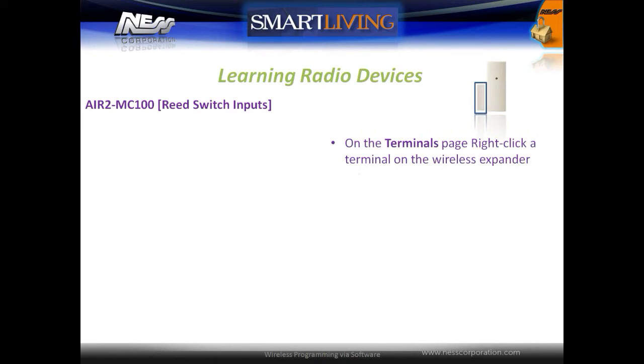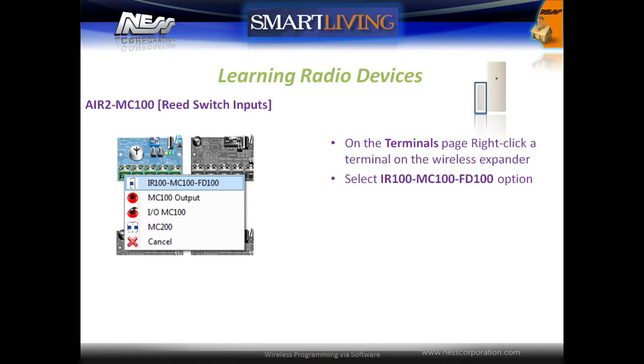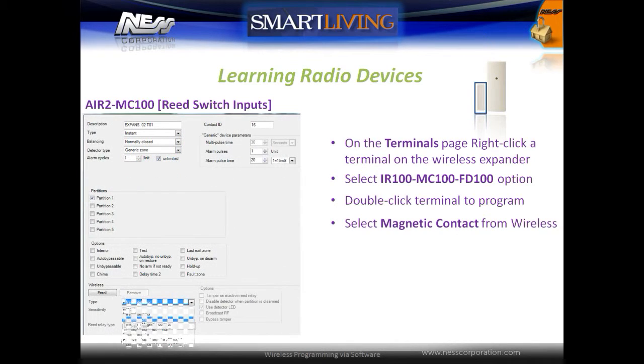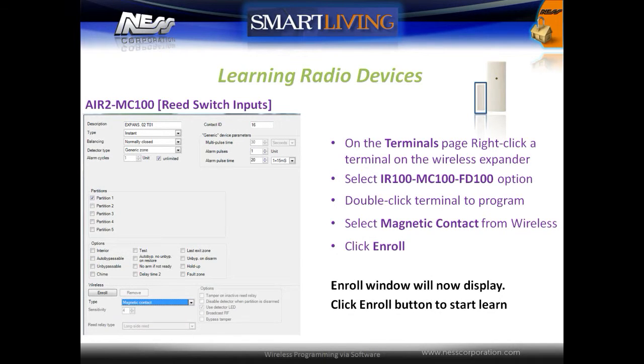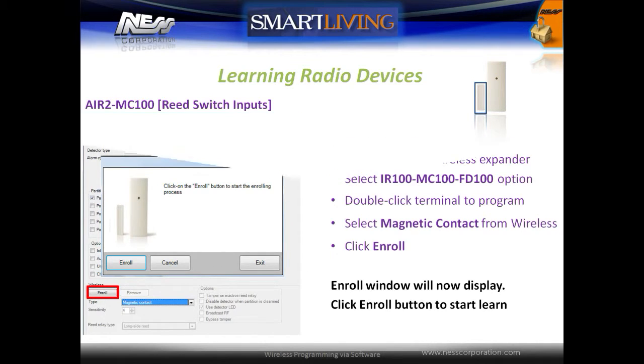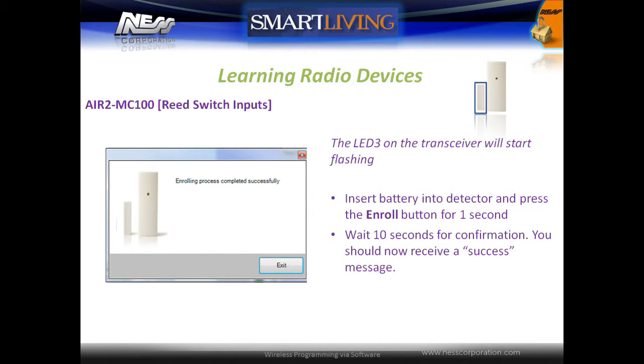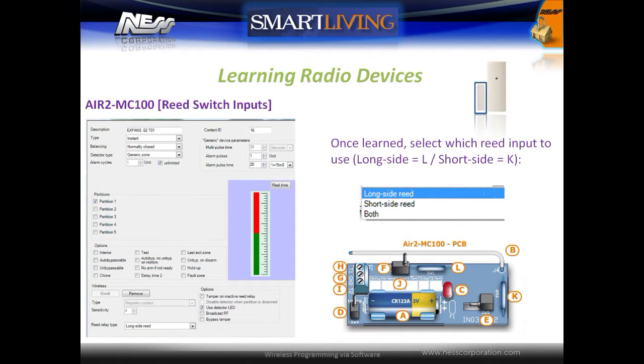To learn as a reed switch, on the terminals page right click on a terminal on the wireless expander, select the IR100 option, and double click to open the programming window. Under the wireless programming section, select the type as magnetic contact. Click the enroll button to enroll the device. Once the system is in enroll mode, the transceiver's LED 3 will start to flash — press the enroll button on the device. After about 10 seconds, a message should confirm that the device was enrolled successfully. Once learned, select which reed input will be used.